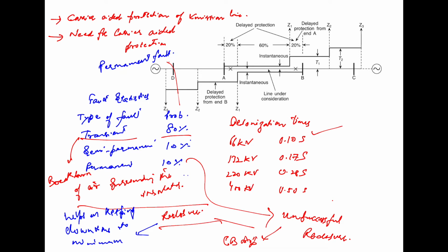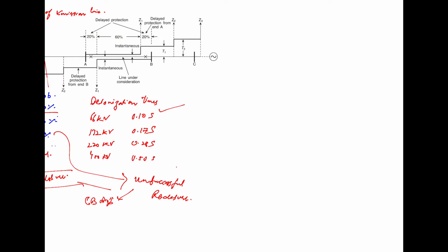The recloser has different implications on low voltage, high voltage and extra high voltage systems. In the low and medium voltage systems, a maximum of 3 consecutive reclosers are allowed, and if the fault persists even after the third recloser, and the third recloser fails, the circuit breaker is locked out and no more reclosers are allowed.